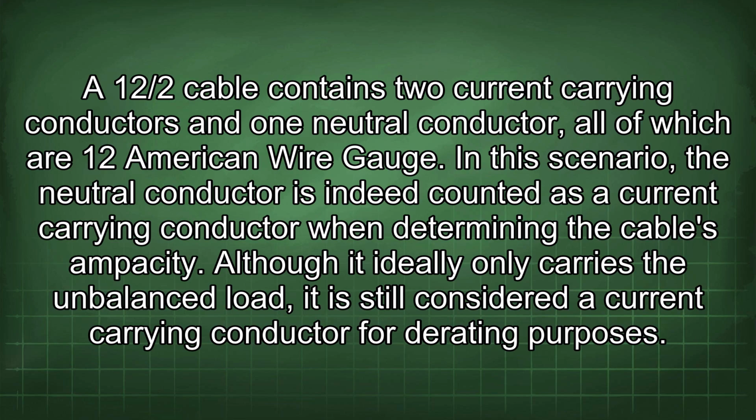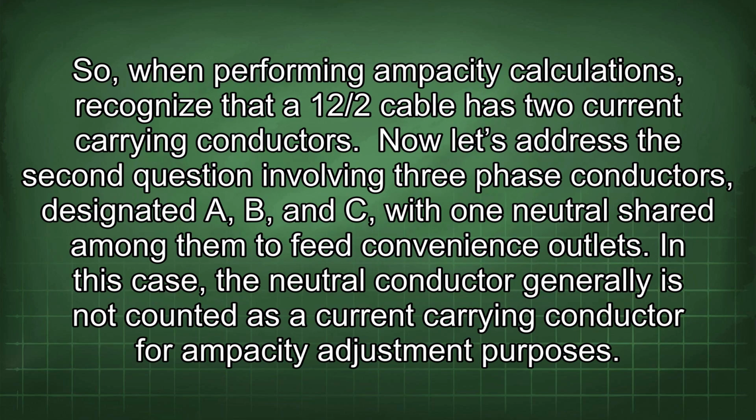Although it ideally only carries the unbalanced load, it is still considered a current carrying conductor for derating purposes. So, when performing ampacity calculations, recognize that a 12/2 cable has two current carrying conductors.